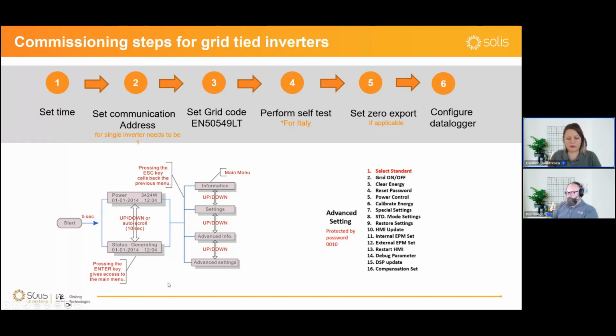But for each country, we have different types of grid codes. Normally, for the countries in the European Union, we have a variation of the EN 50549, which can be marked with some letters. For example, LT is for Lithuania, and PL for Poland. But for those countries where the grid code deviates more from the EN 50549, we have specific grid codes designed for that. The next step, if you want to set up zero export, is to enable those settings as well. And the last is to configure the data logger.